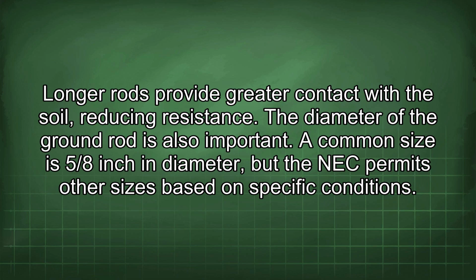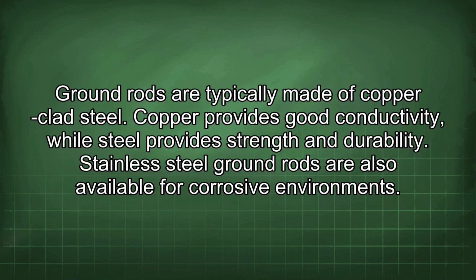The diameter of the ground rod is also important. A common size is 5/8 inch in diameter, but the NEC permits other sizes based on specific conditions. Ground rods are typically made of copper-clad steel. Copper provides good conductivity, while steel provides strength and durability. Stainless steel ground rods are also available for corrosive environments.